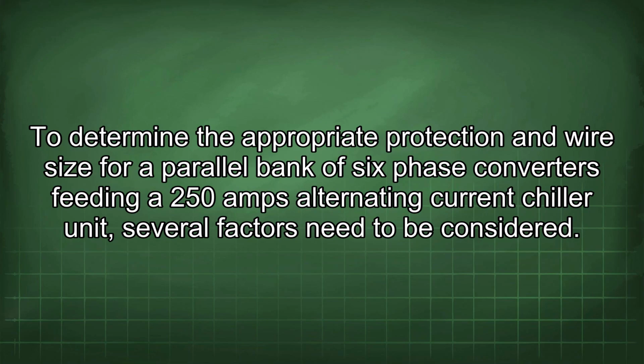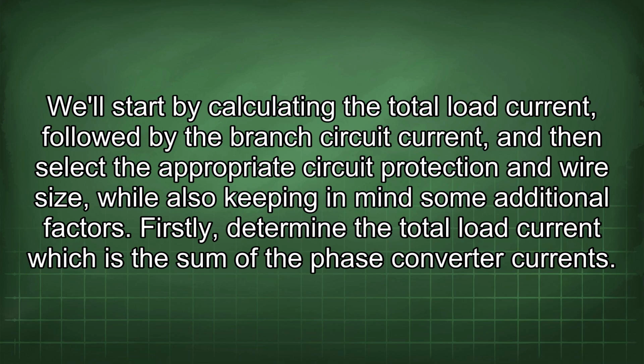To determine the appropriate protection and wire size for a parallel bank of six phase converters feeding a 250 amps alternating current chiller unit, several factors need to be considered. We'll start by calculating the total load current, followed by the branch circuit current, and then select the appropriate circuit protection and wire size, while also keeping in mind some additional factors.